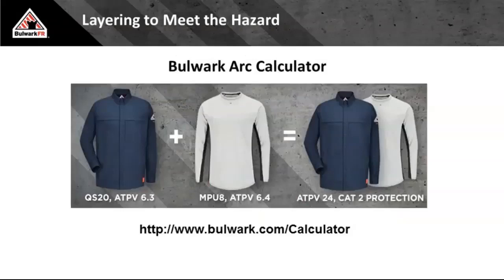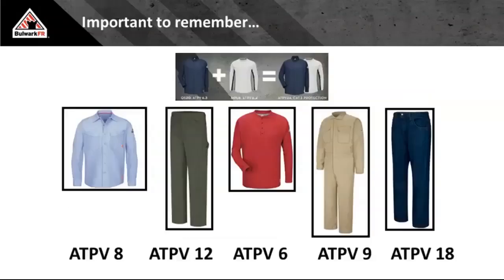Lots of companies have done their calculations for you. If you're wearing their product over their base layer, they're going to give you a number. For example, here I have a Cat 1 shirt, a Cat 1 base layer, 6.3 ATPV, a 6.4 ATPV. Those are two Cat 1 garments when worn independently. Wear them together with the shirt over top of the base layer, and that combination is 24, which is Cat 2, which is just below Cat 3. So a significant increase in performance.